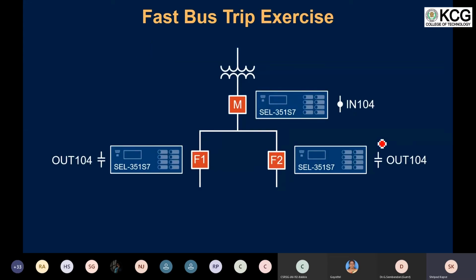So in a conventional way, if you look from the operation point of view, and if you take the cyber related issues out of it, I'm just explaining how this system is going to operate. Here we have a couple of relays on the outgoing feeders, and there is a relay on the incomer. For any fault that occurs on the outgoing leg, the relay protecting feeder 2 is supposed to trip.